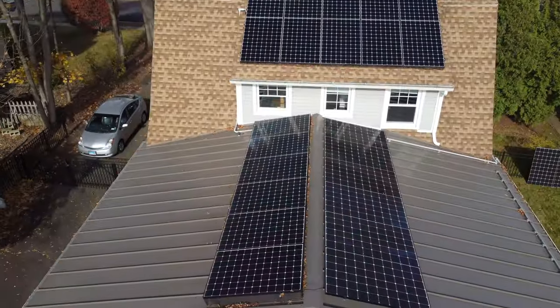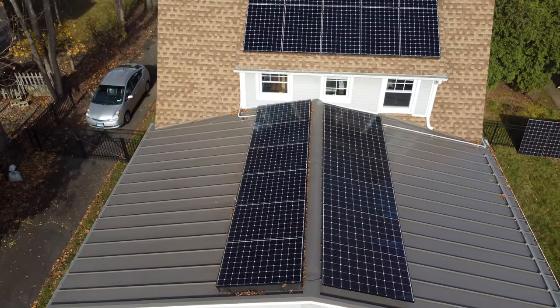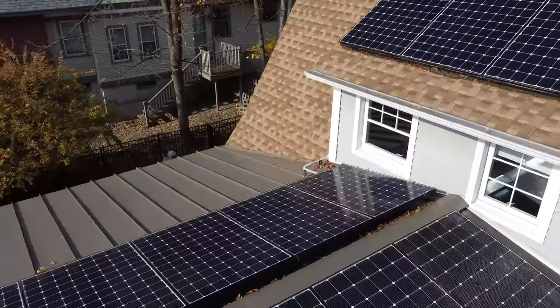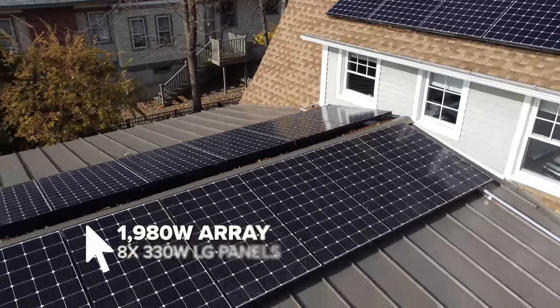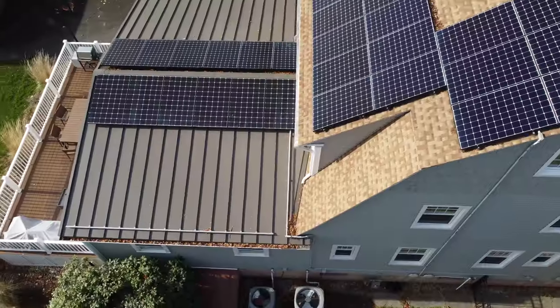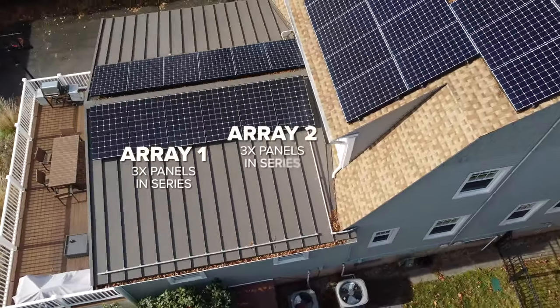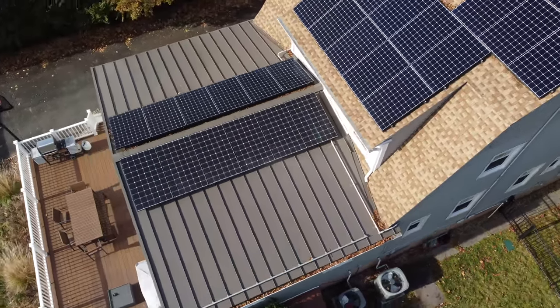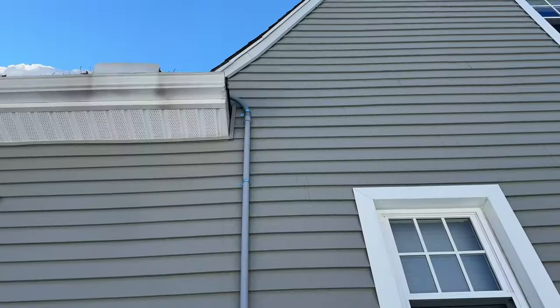I also installed a rooftop array that has 6 of these solar panels, but to get a look at that, we need to go up on the roof. This fall, I installed 6 of these LG panels on my metal roof, so I have a proper array that can be used with the Ultra. It's this array here. I chose to wire these as 2 separate arrays of 3 panels each, so I could stay under the 150 volt limit of many power stations I have.